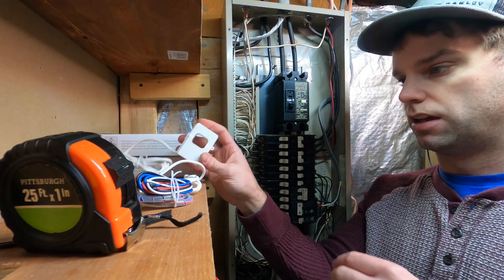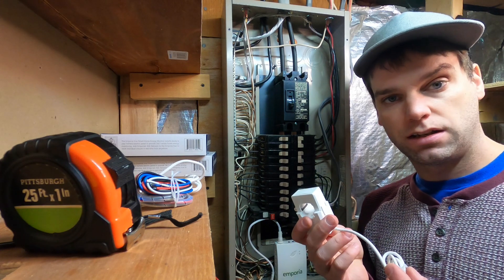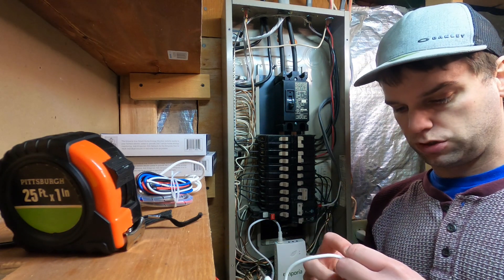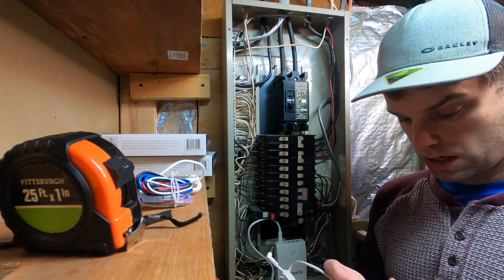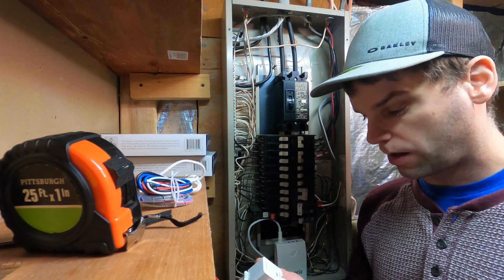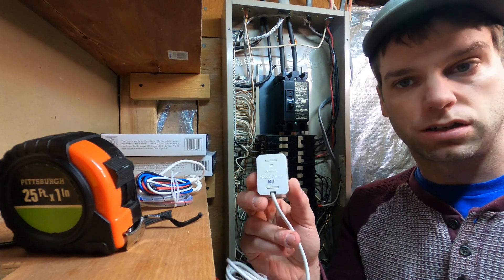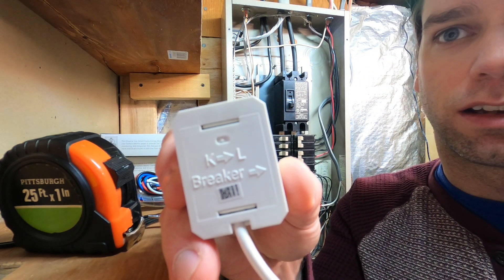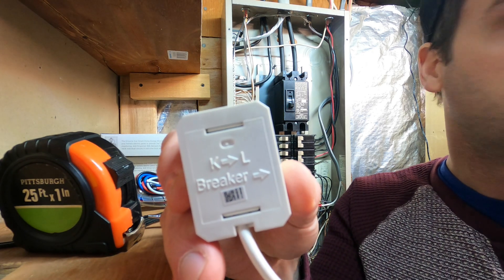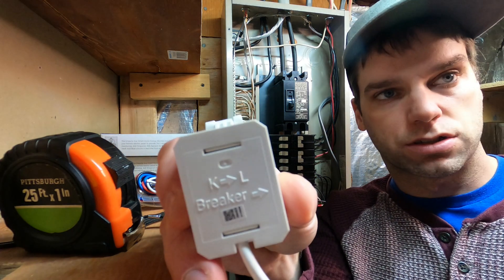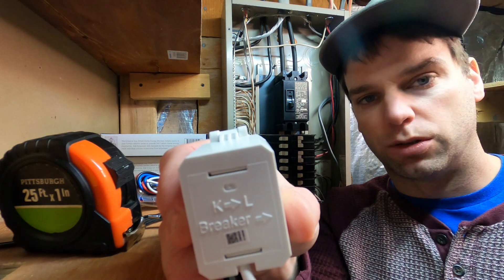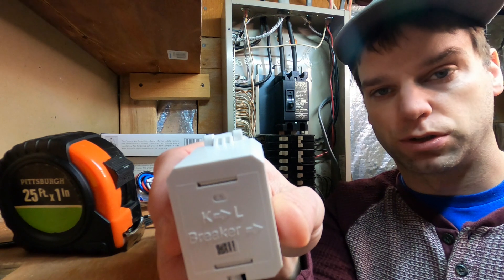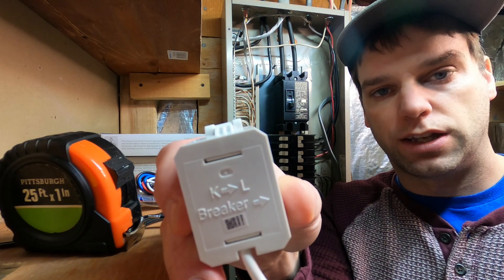All right, the next step and probably the most dangerous one of this whole process is to take these main units and I'm going to connect them up over top of those breakers. Now there's only one thing that you need to worry about with this and that's getting the proper orientation. I'll bring this in close. You can see there is a K to L line and the K needs to be on the service side. The L is your load side. I don't know what K stands for, but L is probably load. So just make sure that it's pointing towards your load or your breakers. It's labeled pretty clearly, but just make sure you get that right.